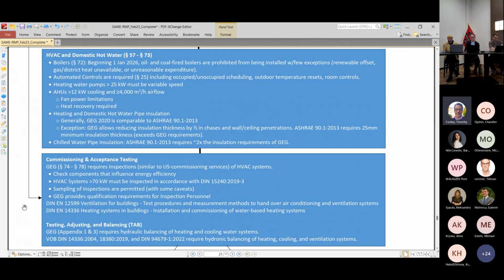It's going to want pumps to include variable frequency drives. It's going to provide some fan power limitations for ventilation systems, making sure that the ratio of static pressure in your duct distribution system versus the airflow you're pushing through is not energy wasting. It's going to prescribe minimum insulation requirements for heating and chilled water and domestic hot water piping. This is a pretty easy thing to compare with ASHRAE 90.1, the US requirements. For heating piping, they're very comparable. The Gebäudeenergiegesetz is slightly better. For chilled water, the ASHRAE 90.1 requirement is an instance where the ASHRAE requirement exceeds what's in the Gebäudeenergiegesetz.